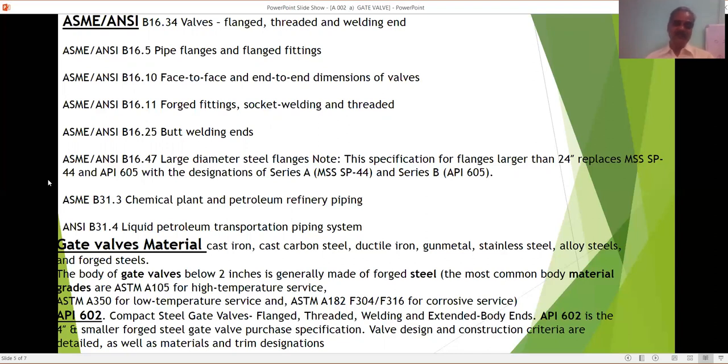ASME B16.47 large diameter steel flanges. This specification for flanges larger than 24 inches, replaces MSS SP 44 and API 605, with the designations of series A, MSS SP 44 and series B, API 605. This is replacing.